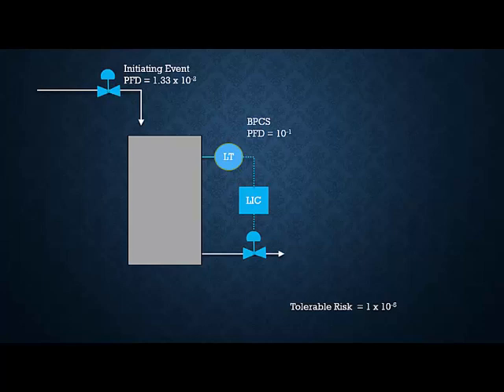And that's where your SIF comes in. Your safety instrumented function, for the sake of argument for this one, we're going to add a separate level transmitter, separate logic solver, separate shutoff valve. So on this system, if level goes high, the controller is going to close the valve. So you know your tolerable risk. You know what your risk is without the safety system. So through the magic of algebra, you can figure out that the PFD needs to be 7.52 times 10 to the negative 4th. Because if you multiply all three of those together, you get the tolerable risk. So your probability of failing for that SIF needs to be at least 7.52 to the negative 4th. So how do you know that what you put in, the transmitter you use, the valve you use, that's all going to give you the right odds, give you enough protection? Well, to answer that, we're going to dive into some more terminology.